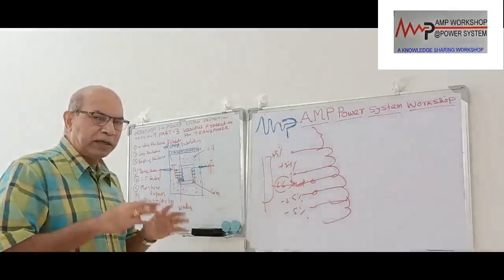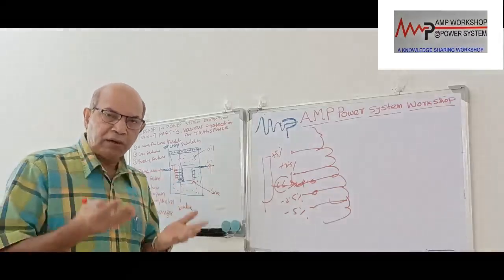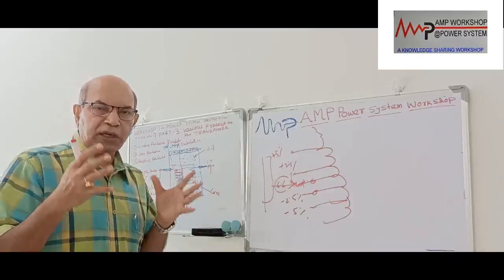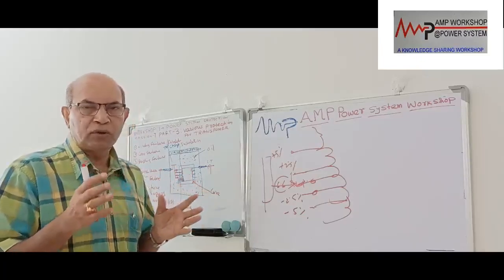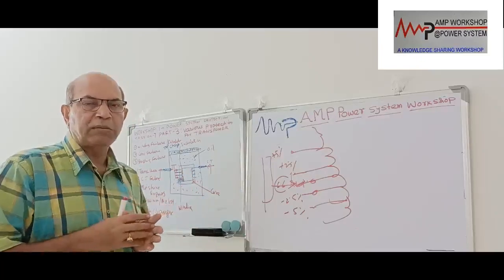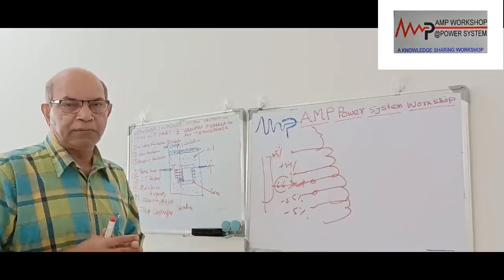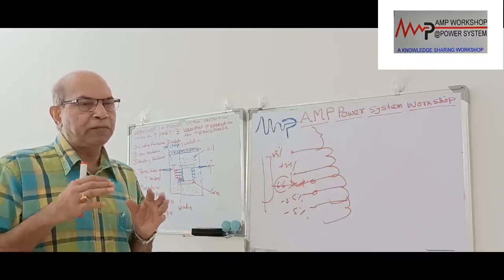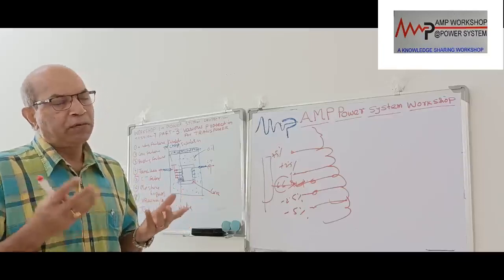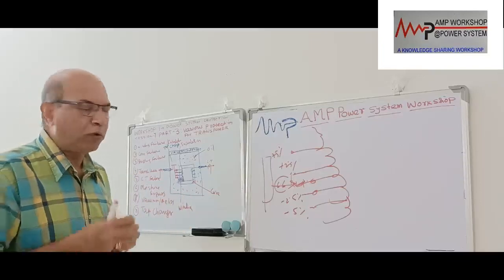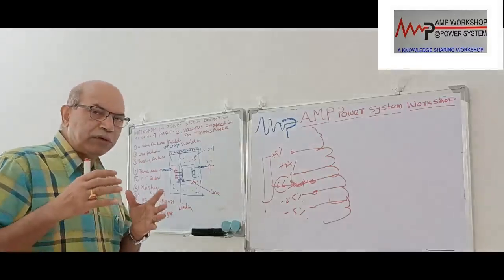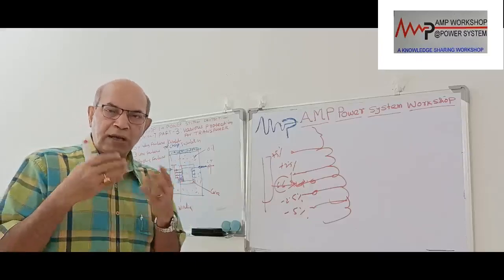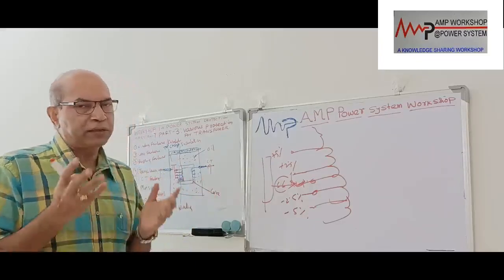Then the entire core can fail due to heating of the core or during transport of the transformer, because the transformer is sealed with oil when it comes to the site, and we have no control over that. During transport there may be huge vibration on the transformer, and that may loosen the core. If the core bolts all get loosened, then some time after installation, the core can fail. Or if the core is used on a low frequency voltage, then high flux will be produced, which produces high heating, as we have already discussed. In that case, the core can fail.